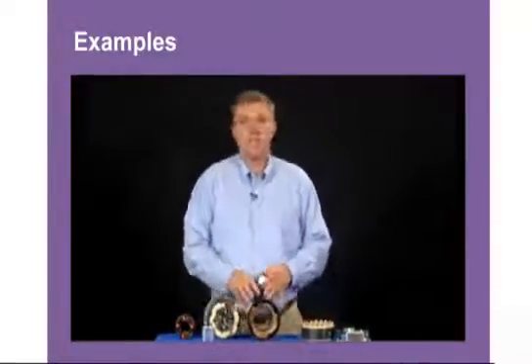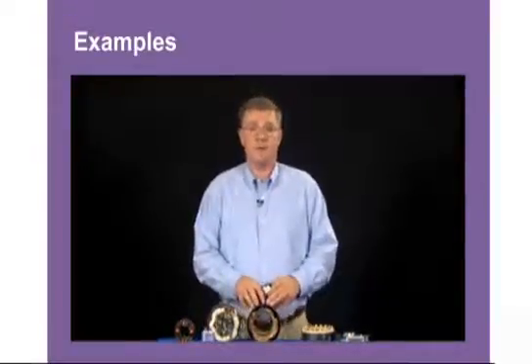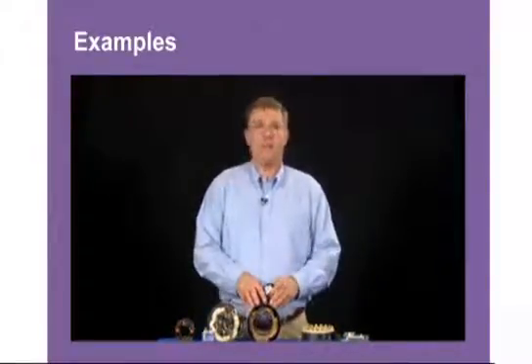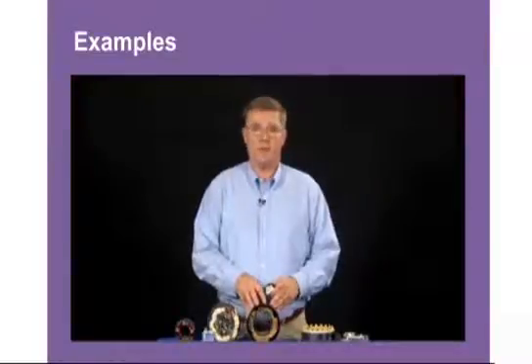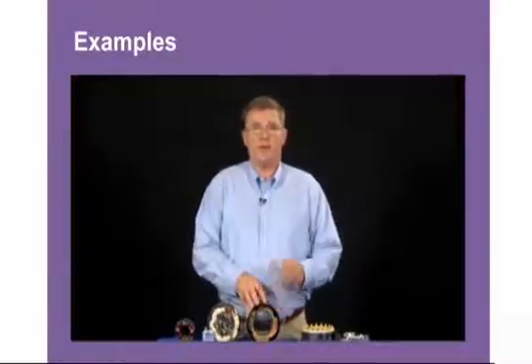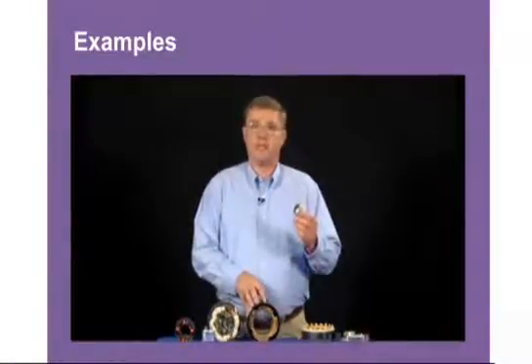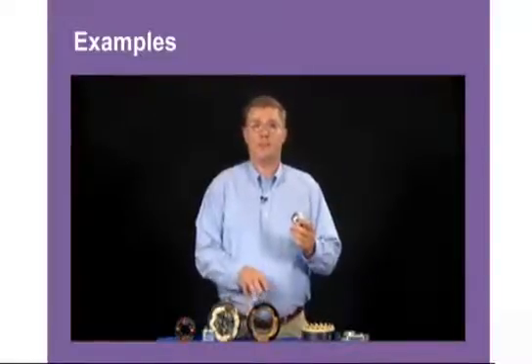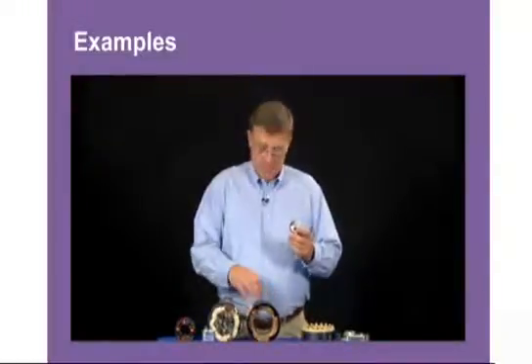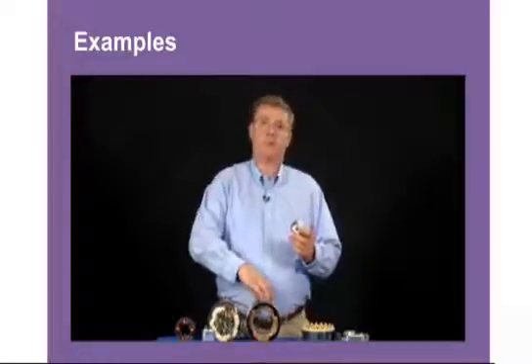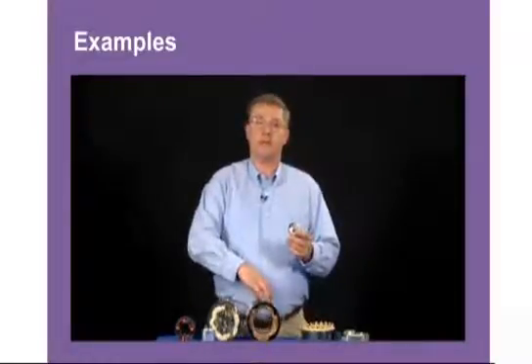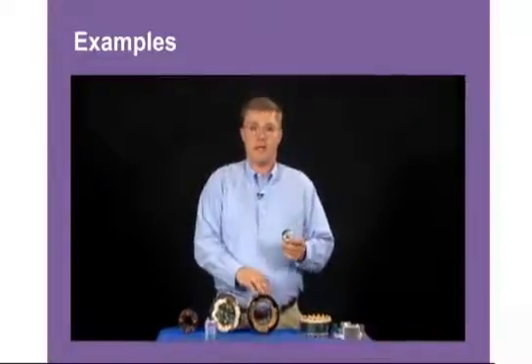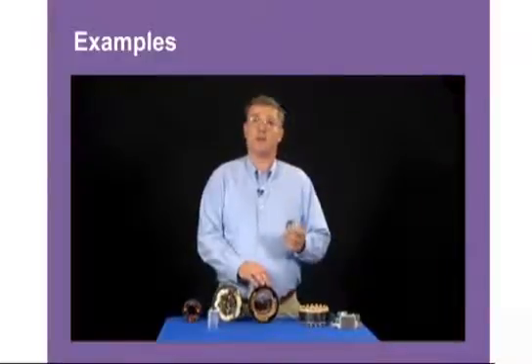There are three types of split phase motors. The first is the standard split phase. The second is a capacitor start motor — it still has a centrifugal switch and is still a split phase motor, but now we put a capacitor into the start winding. You typically see a dog house on top of this with a capacitor inside, wired directly into the start winding. This allows for a little greater starting torque and a little more efficiency.